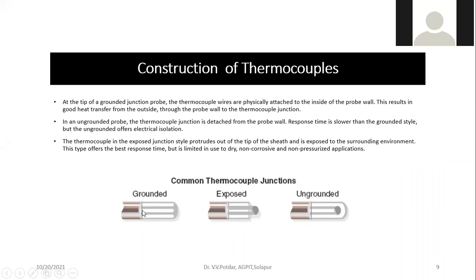As you can see, this is the pair of dissimilar metals. When it is connected to ground, this is the junction of two dissimilar metals. When connected to the ground, it is called the grounded type of thermocouple junction. In the ungrounded type, I have one metal, another metal, the junction of two dissimilar metals, but this junction is not connected to the ground - this is called ungrounded.